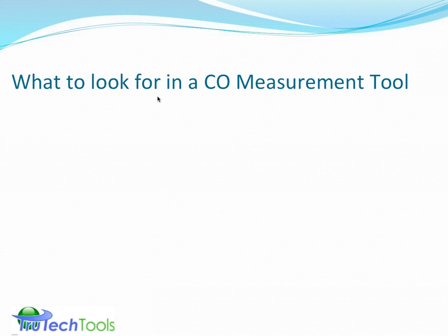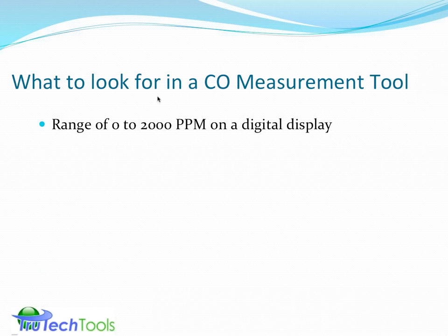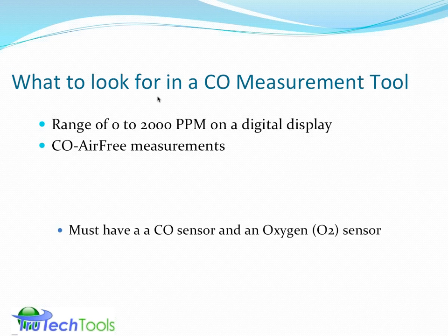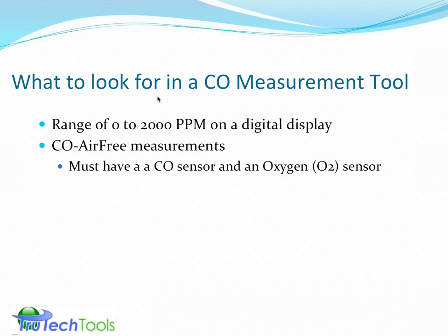Let's pull out and summarize the parameters we're talking about, what to look for in a carbon monoxide measuring instrument. We're looking for a range of 0 to 2,000 parts per million on a digital display. Pretty easy requirement to meet. We're looking for CO air-free measurements. That pretty much locks you into combustion analyzers. So I'm going to name some names here: things like Monoxor 2s, Monoxor 3s, Monoxor Pluses would not qualify as a CO measurement tool for this BPI standard because they do not have oxygen calculations. So it must have a CO and an oxygen sensor present. You could use one of those tools I mentioned previously with an oxygen analyzer and do the math offline yourself, but that's difficult.